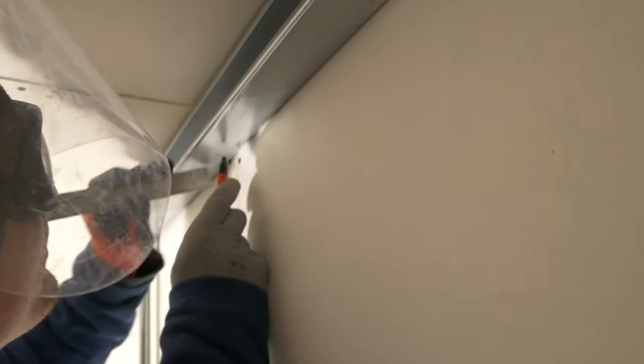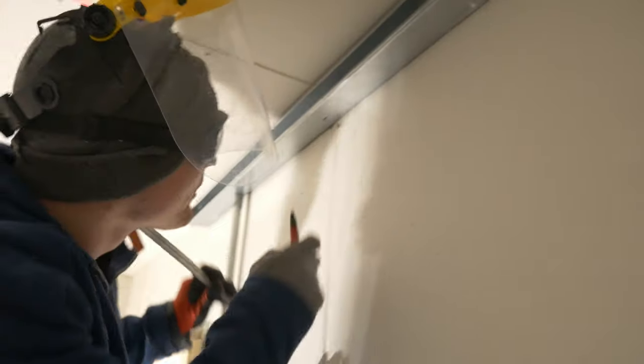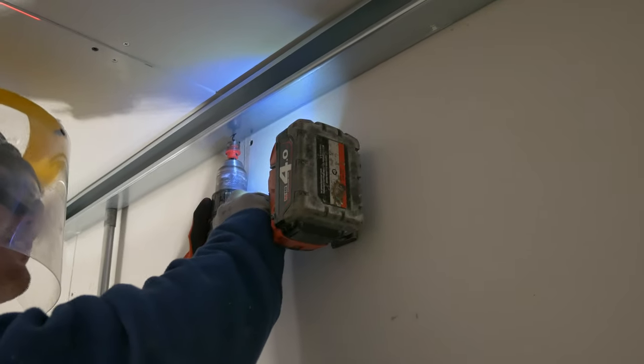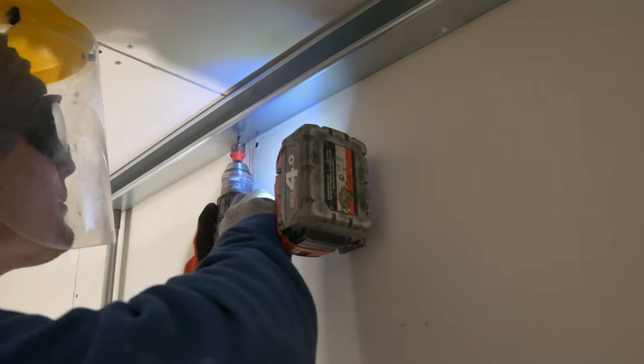So you can see with this one, he's marking and measuring for the entry hole into the trunking. Now you can do this with little tricks using saddles and couplers or a length of tube and mark the hole center onto the trunking. But my preferred method is always to take a measurement and mark it onto the containment. That's the way I've always done it. And I think it's as good as any. It's as fast as any other method, in my opinion.